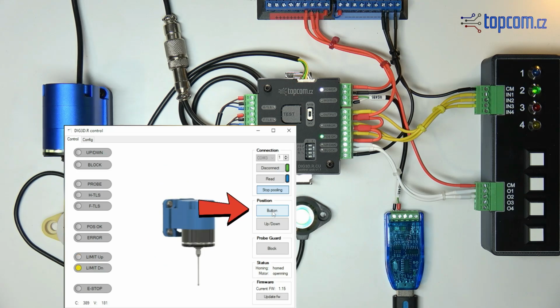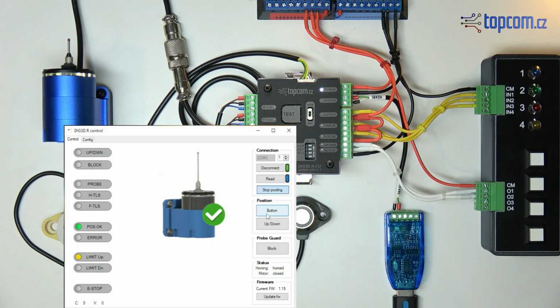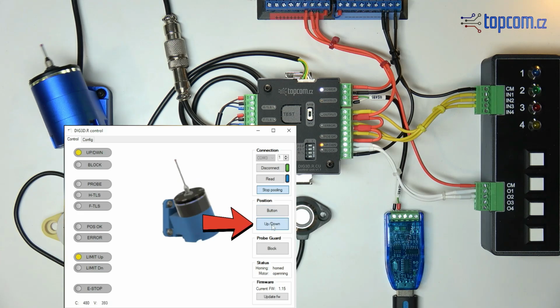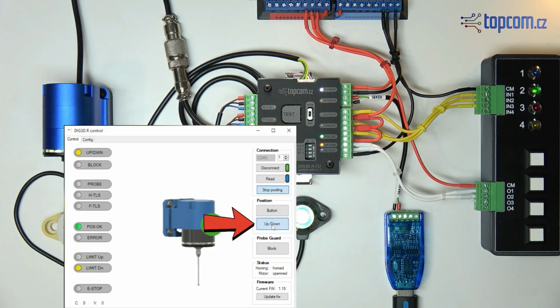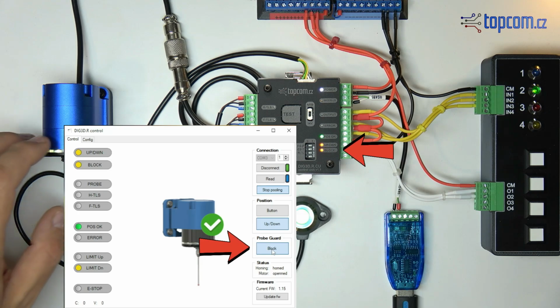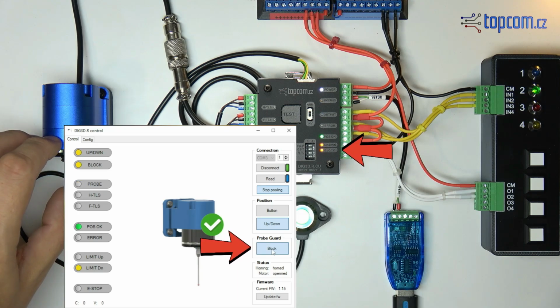Clicking the button in the application performs the same function as pressing the physical button or the test button on the control unit. Just like the button function, you can also control the input that sets the probe position and the input that blocks the probe guard function. When an input is activated via Modbus communication, the corresponding LED on the control unit lights up.